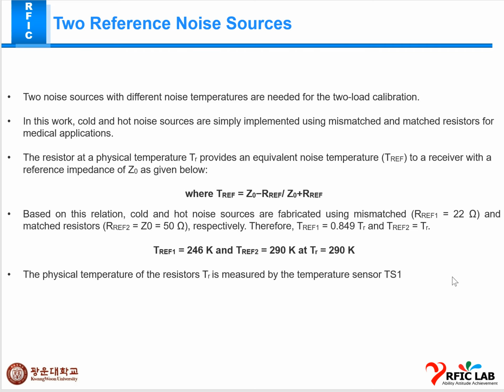Now the TR reference 1 value is 246K, and TR reference 2 value is 290K, and TR equals 290K. This temperature, which is a physical temperature, is measured using a temperature sensor TS1. That's the whole explanation of the two reference noise source.